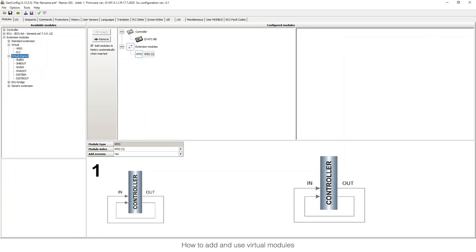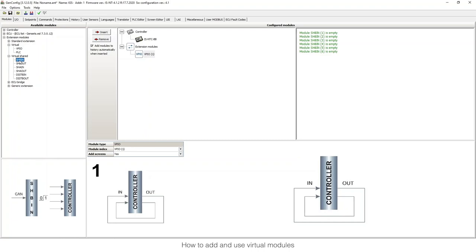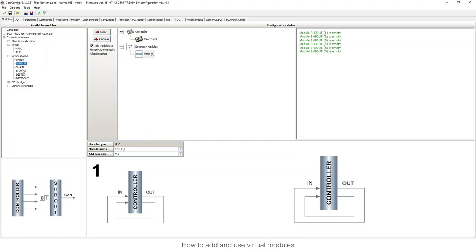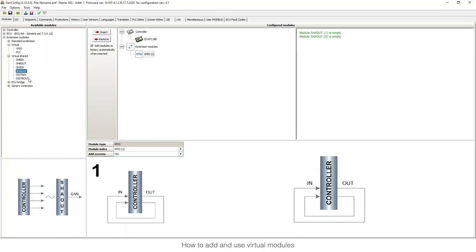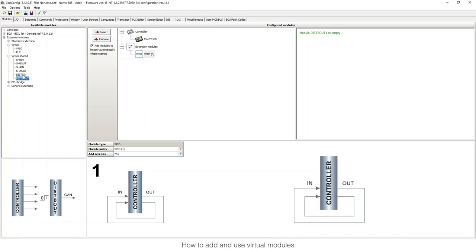Now we are going to talk about virtual shared modules. The PLC part is handled automatically. We'll discuss server binary inputs and server binary outputs — these are connected together. The idea is to pass information from one controller to another that are connected on the same CAN line, without wiring. You need a shared binary input paired with a shared binary output, or a shared analog input with a shared analog output. There are also distributor binary input/outputs, which I will cover at the end.